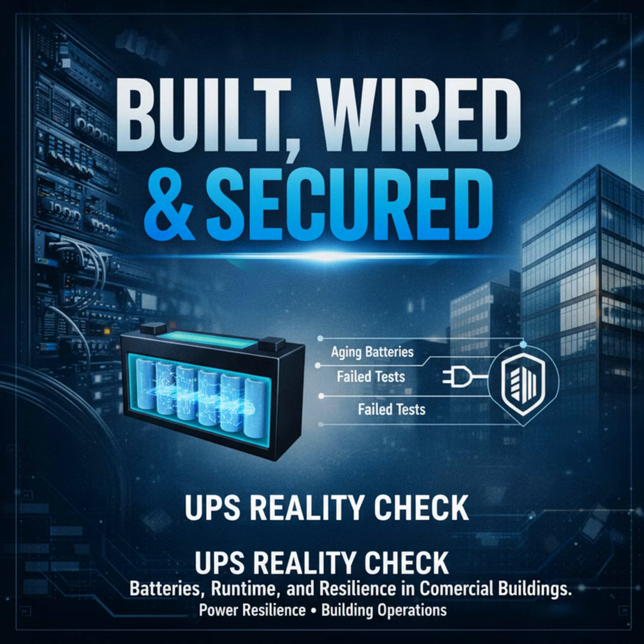Let's dive in. Cold open, picture a short, neighborhood-wide outage, 3 minutes, and the building's UPS was expected to keep critical systems running. Instead, tenant leasing card readers went dead, the lobby doors failed to respond, and a bank of point-of-sale terminals rebooted unpredictably. People were safe, but operations stalled and tenants demanded answers. That's the kind of mismatch between expectation and reality we'll unpack today.